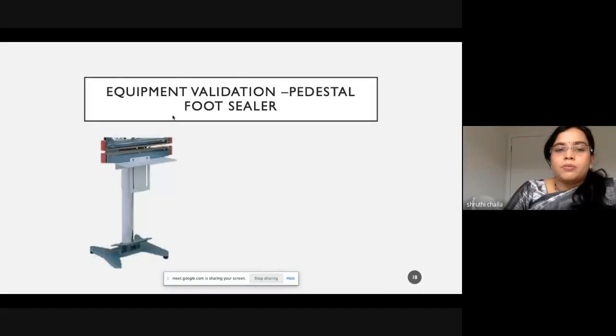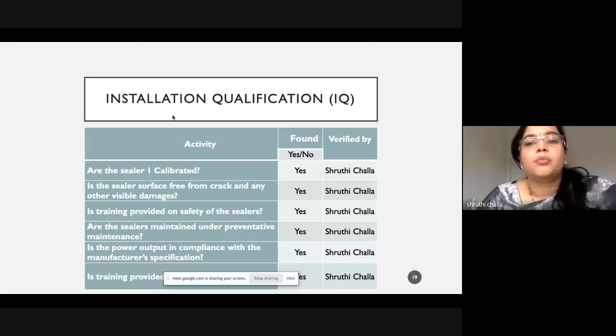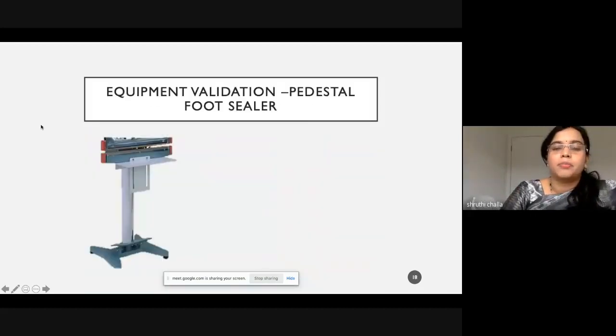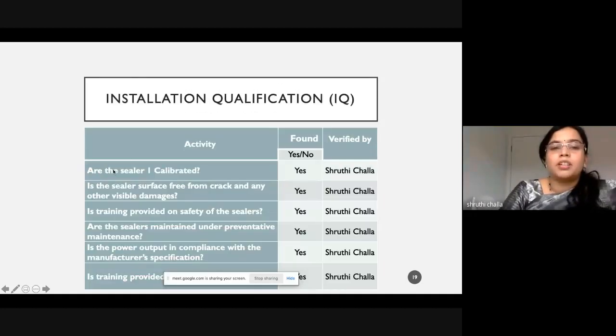Okay, so we bought this equipment. We did all the URS, and we got the functional specification and design specification from the vendor. So we got it, and we want to install, so we perform this installation qualification. So what does this installation qualification include? Because this is such a simple equipment, it doesn't have much for installation qualification. All we are checking here is, because we said we got a temperature probe, we need to have it calibrated. So is the sealer one calibrated? Yes or no? Is the sealer surface free from cracks or any other visible damages?